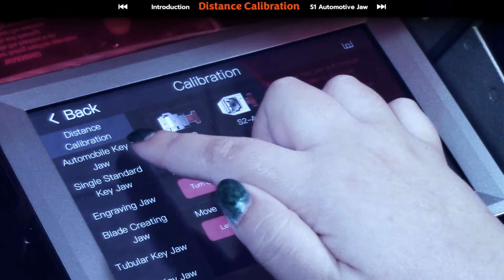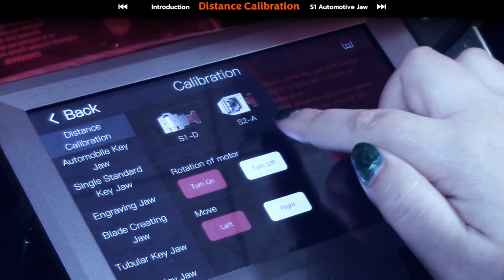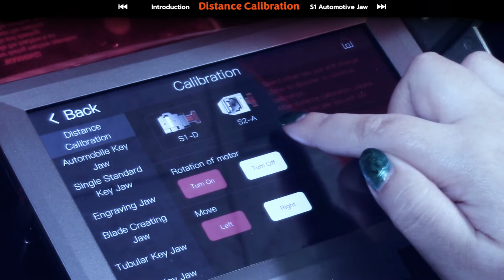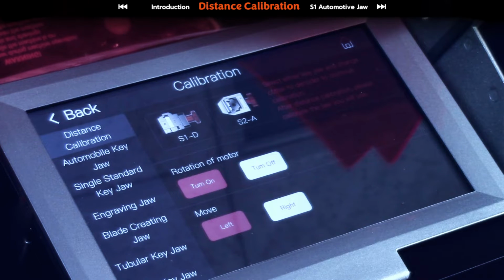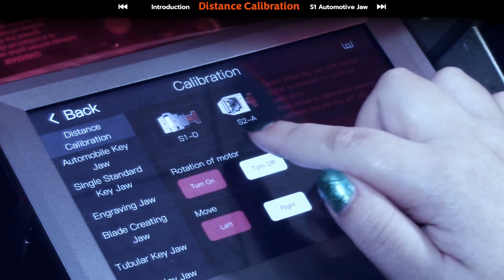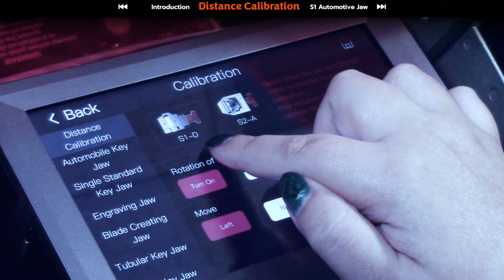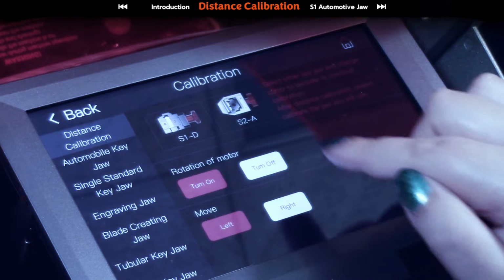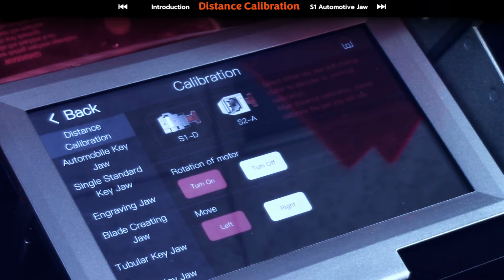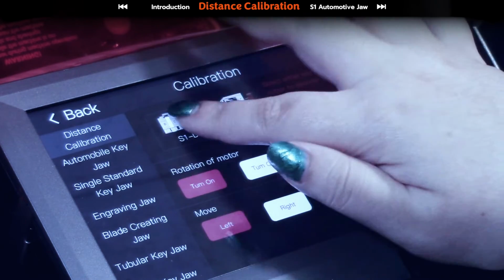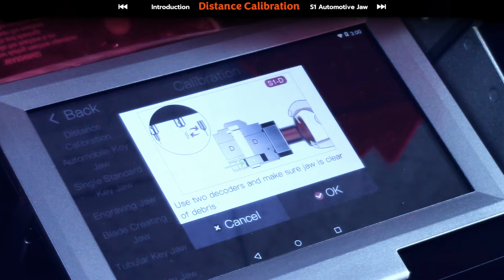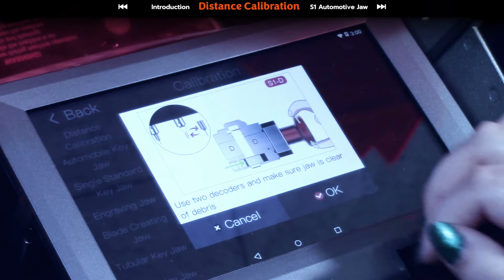And on the screen here, you'll see the very first one at the top is the distance calibration. So there's two options, S1D or S2A. If you're going to calibrate, you only need to do one of these two options. So today we're going to be doing S1D, but if you'd like to and you have both jaws, you can do both. So if you tap on S1D, it's going to show you this picture to kind of guide you on how to clamp the jaw and get everything all positioned for the calibration.